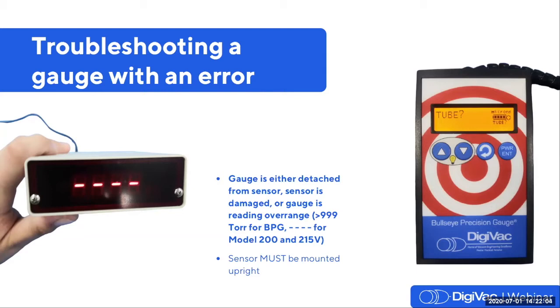So you can simply hold the sensor upright and the reading will adjust to atmospheric pressure in just a few seconds. This is a common technical support issue that I tackle when a customer calls with a brand new gauge right out of the box, ready to use, and is curious as to why they're getting an error message right out of the gate. Meanwhile, they've opened the box on their desk. They've not yet plumbed their sensor into whatever sort of chamber that they're pulling vacuum on, and they'll have this error message, which isn't really an error at all, just merely a misunderstanding about how to correctly hold the sensor.